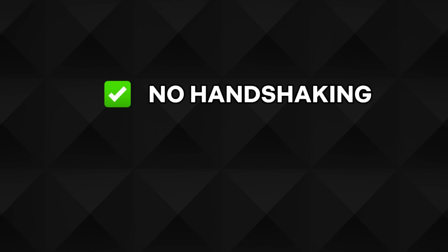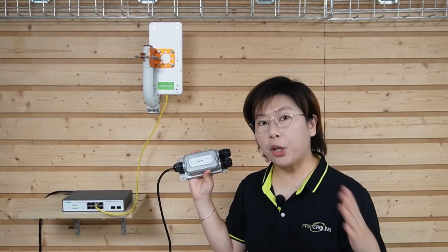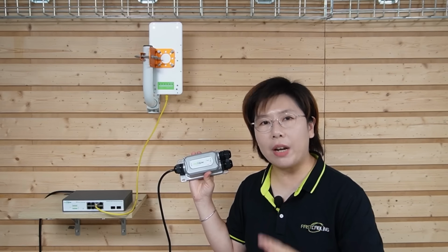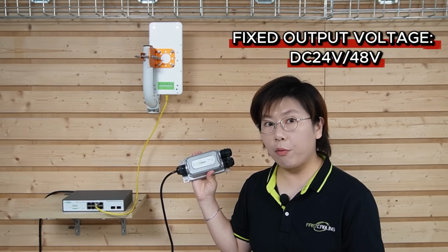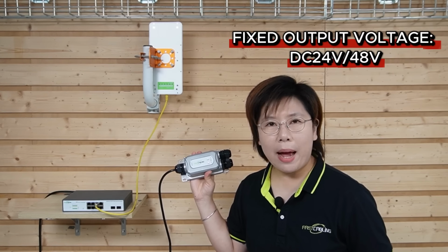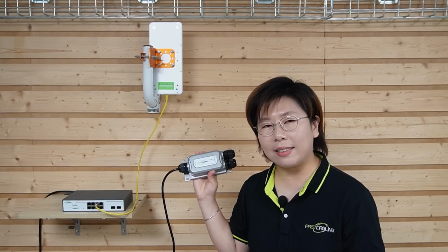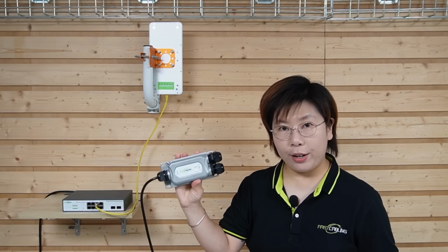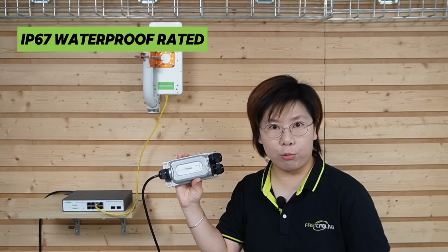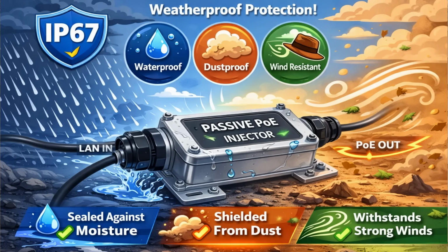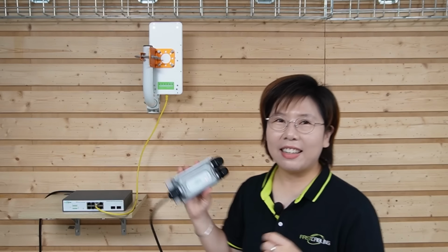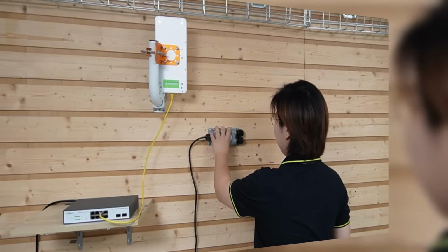No handshaking, no negotiation, just pure reliable juice at a fixed voltage, usually 24 volt or 48 volt, depending on what your bridge needs. And because this one here is IP67 outdoor rated, it's sealed against moisture, dust, and the kind of wind that tries to steal your hat. So without further ado, let's mount it on the board.